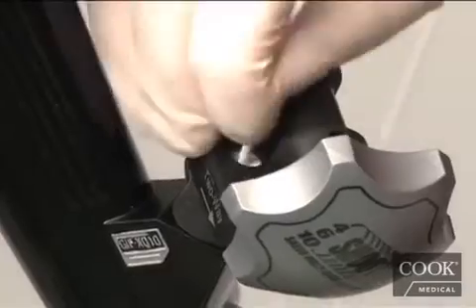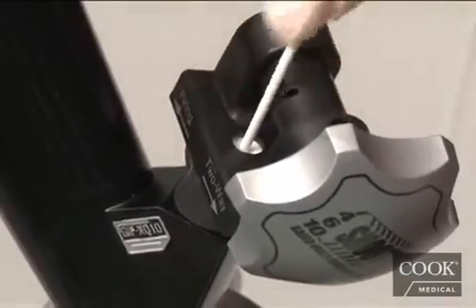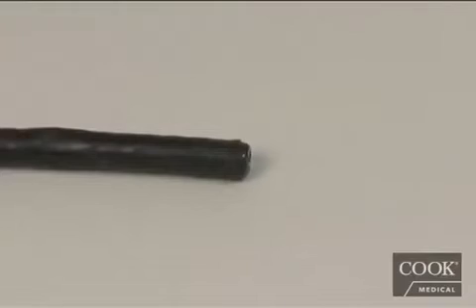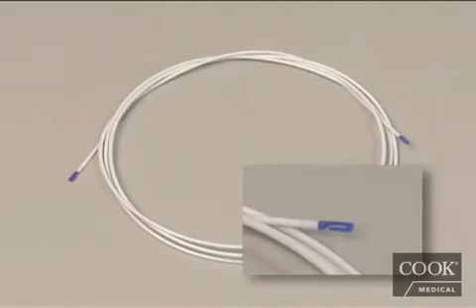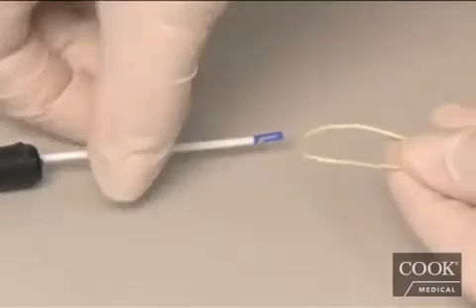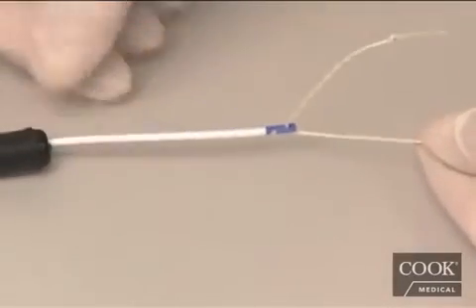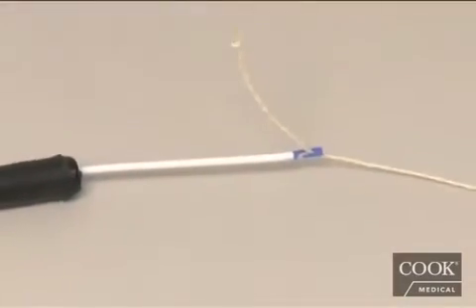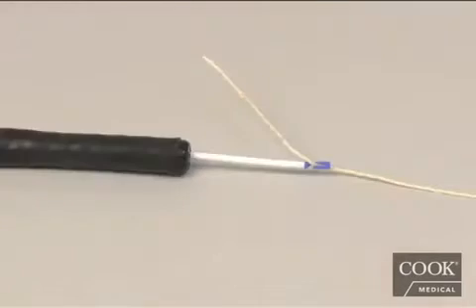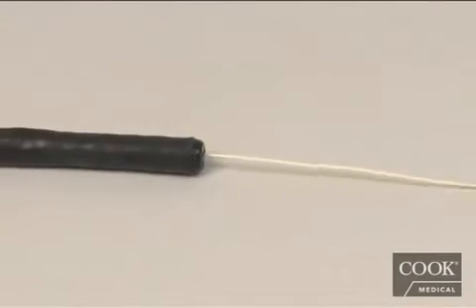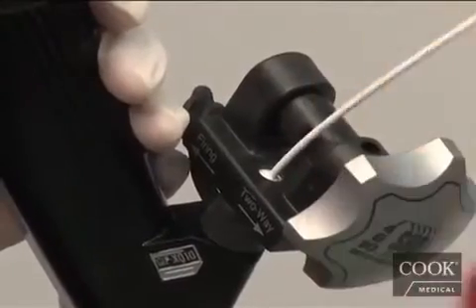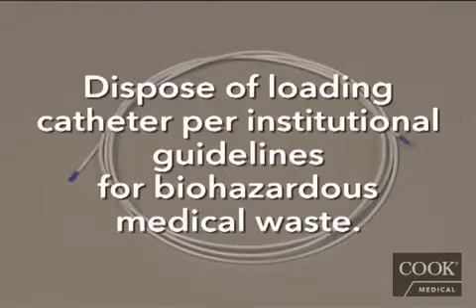Introduce the loading catheter through the white seal in the handle and advance in short increments until it exits the tip of the scope. Note, the loading catheter is identical on both ends and may be introduced either way. Attach the trigger cord to hook on the end of the loading catheter, leaving approximately 2 centimeters of trigger cord between the knot and the hook. Withdraw the loading catheter and trigger cord up through the endoscope and out through the handle. Dispose of the loading catheter per institutional guidelines for biohazardous medical waste.